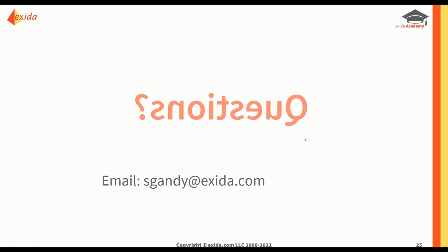How about 2 out of 3? Well, 2 out of 3 becomes more complicated, but again, it's still the same approach. And what I was trying to show you was using simplified equations. The 2 out of 3 equation is much more complicated. Again, typically you won't use simplified equations. You'll be using a Markov model to look at the safe and dangerous failures and using a tool such as exSILentia. So I've just used these simplified equations for comparisons to give you a feel for what the impacts are.